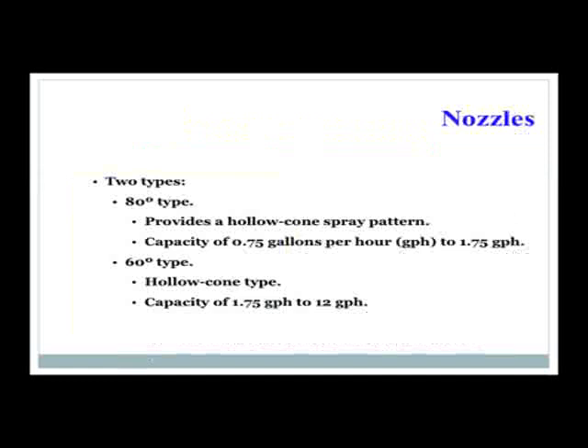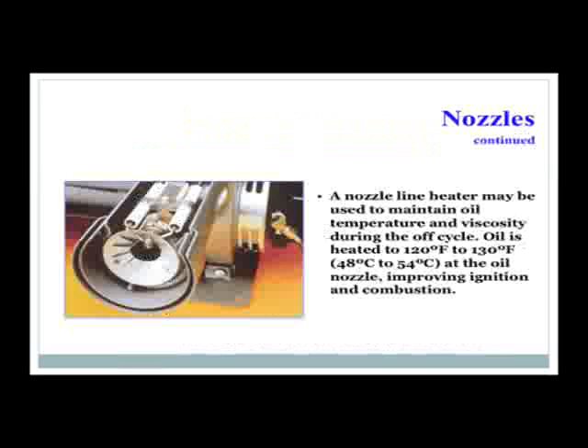With nozzles, we have 2 types of nozzles. The 80-degree type provides a hollow cone spray pattern, with a capacity of 0.75 gallons per hour to 1.75 GPH. Another type is the 60-degree type, the hollow cone type. Its capacity is again 1.75 GPH to 12 GPH. The nozzle line heater may be used to maintain oil temperature and viscosity during the off cycle. Oil is heated to about 120 degrees or 130 degrees at the oil nozzle and improves ignition and combustion.